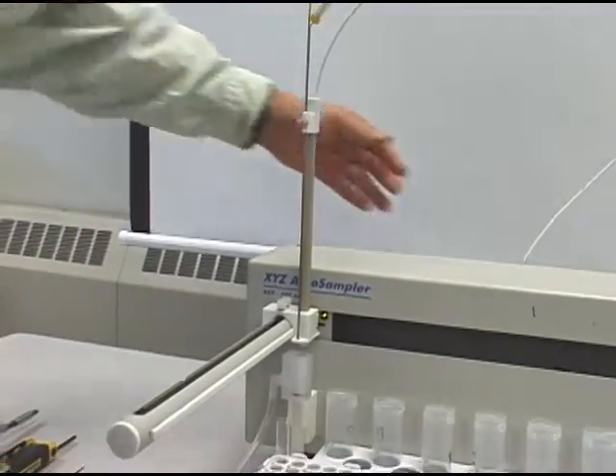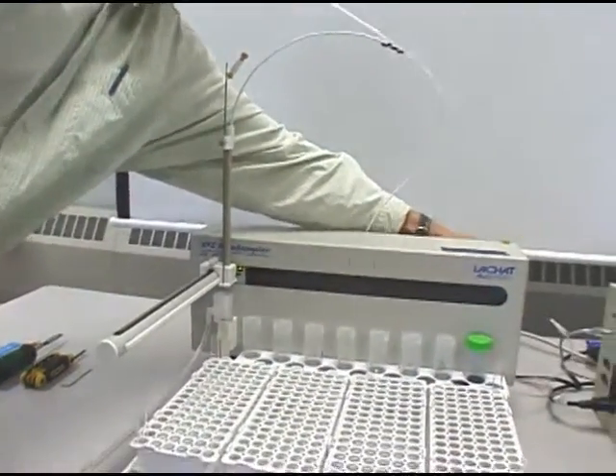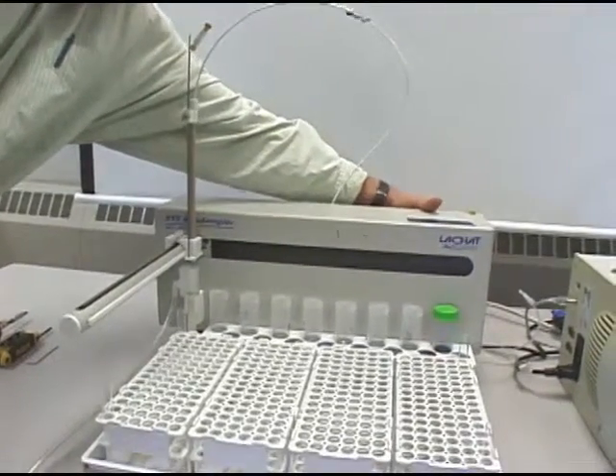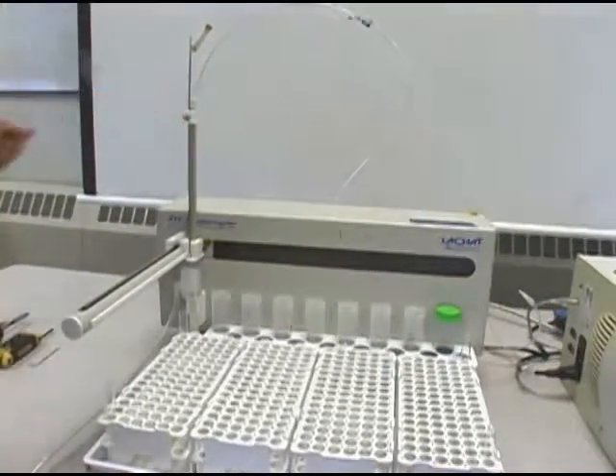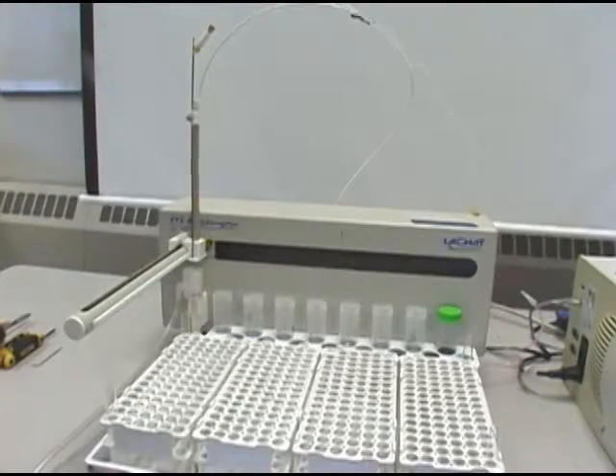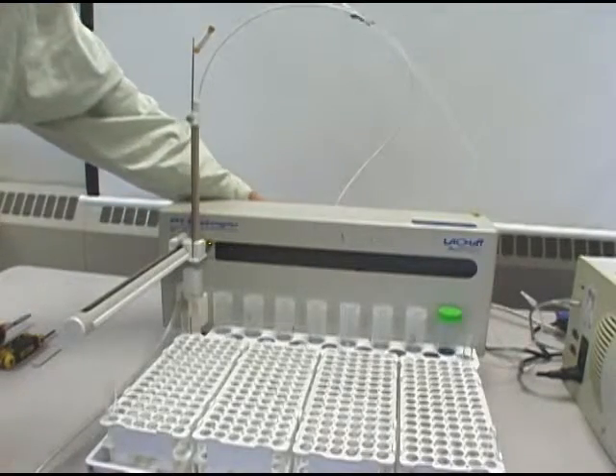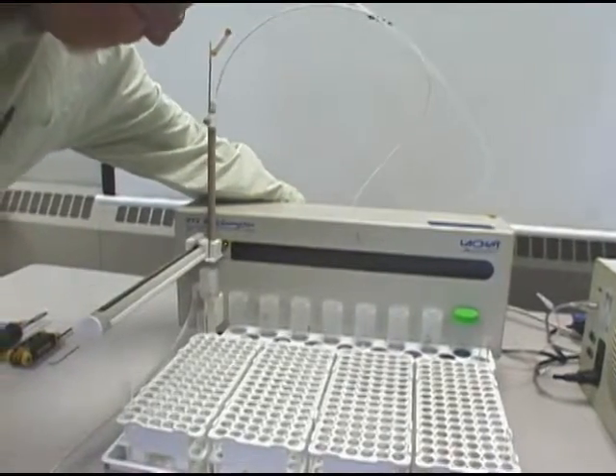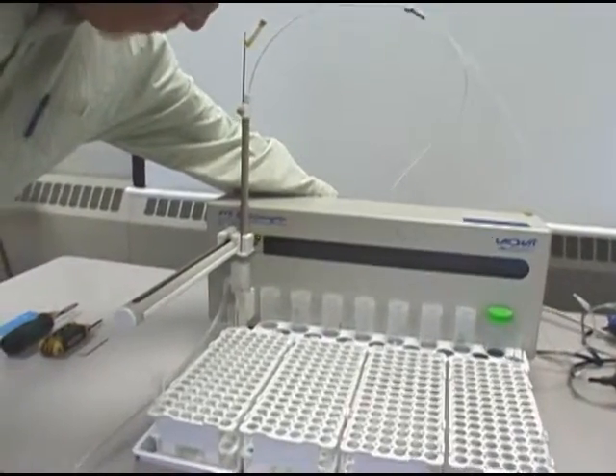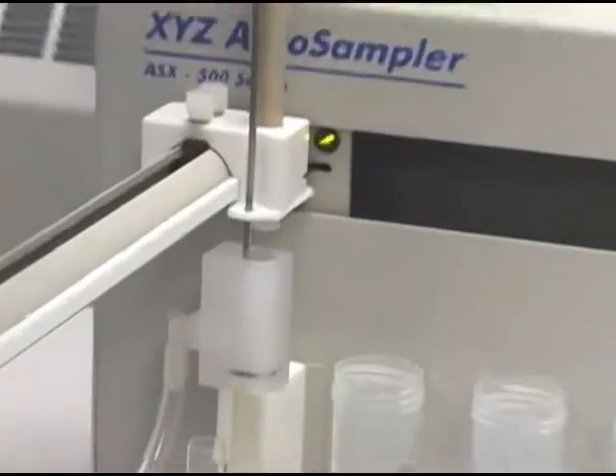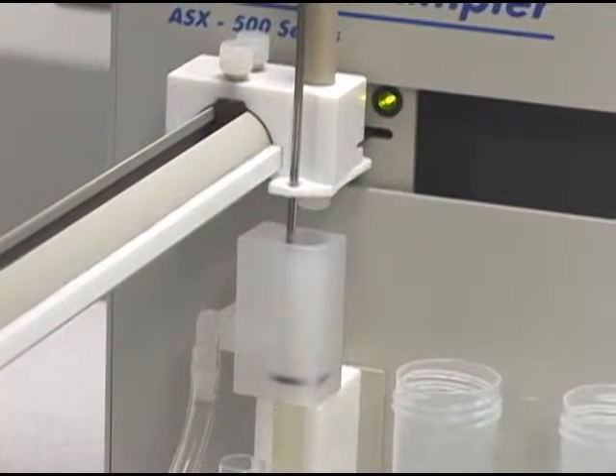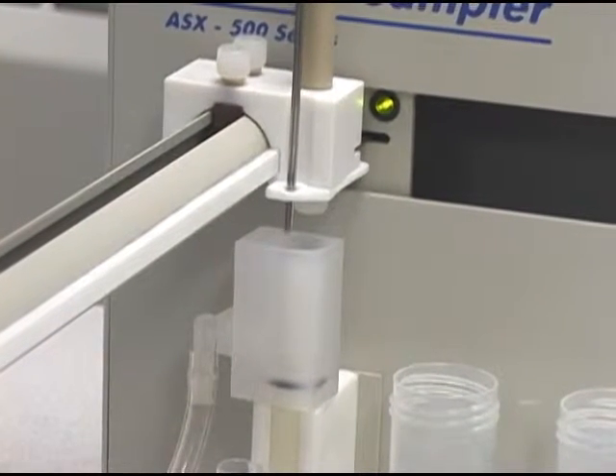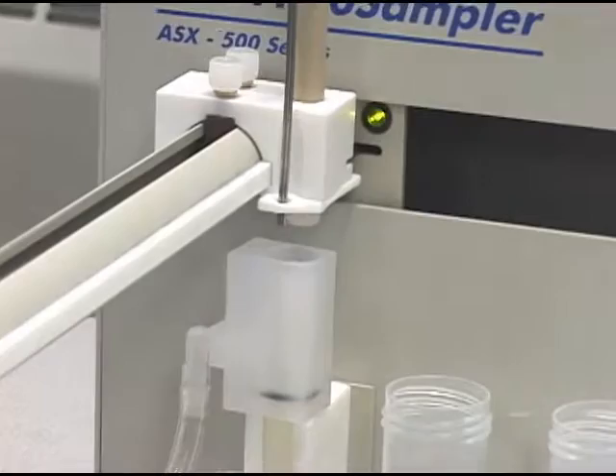And now what I'll do is I'll turn the instrument off and then turn it back on, and it will reset itself. I can then turn the wheel in the back to see how close the probe now is in alignment. You can see that it's still off, and we'll go ahead now and demonstrate how to set the alignment of the wash bath.